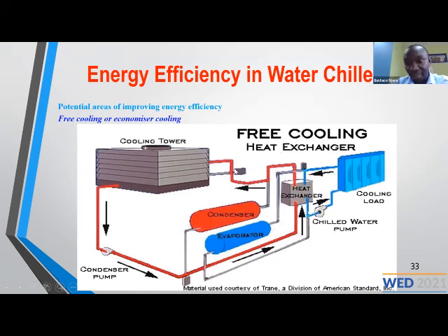I know you're asking why we don't cool using the water from the cooling tower directly. It's not good to mix the chilled water and the water from the cooling tower, because you can see the cooling tower is open. So this water sometimes gets dirty, and we don't want to make the chilled water dirty. That's why we use a heat exchanger to avoid mixing the two waters.